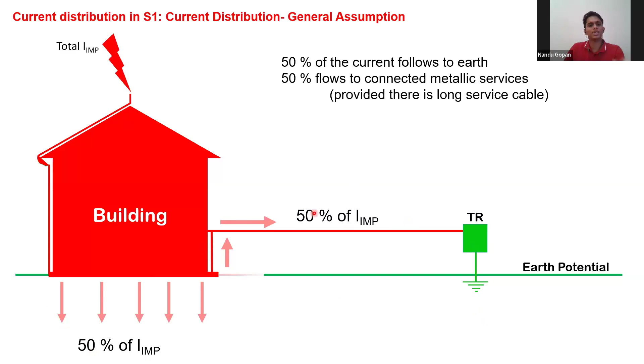So for I impulse, there is only one service line. This I impulse for the SPD, if you are doing the lightning protection as per LPL1, then you have to have it for 100K, 75K, or 50K, depending on the case.